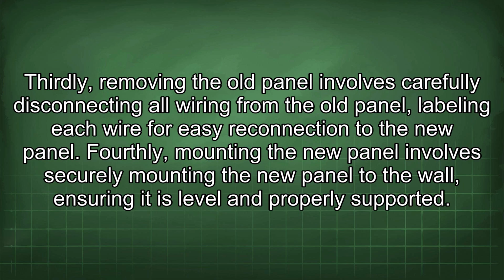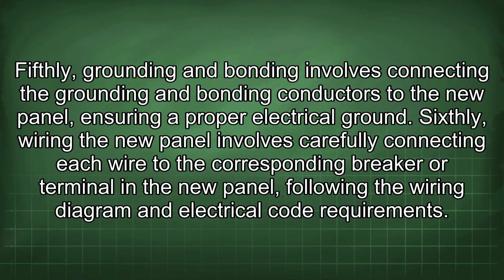Thirdly, removing the old panel involves carefully disconnecting all wiring from the old panel, labeling each wire for easy reconnection to the new panel. Fourthly, mounting the new panel involves securely mounting the new panel to the wall, ensuring it is level and properly supported. Fifthly, grounding and bonding involves connecting the grounding and bonding conductors to the new panel, ensuring a proper electrical ground. Sixthly, wiring the new panel involves carefully connecting each wire to the corresponding breaker or terminal in the new panel, following the wiring diagram and electrical code requirements.